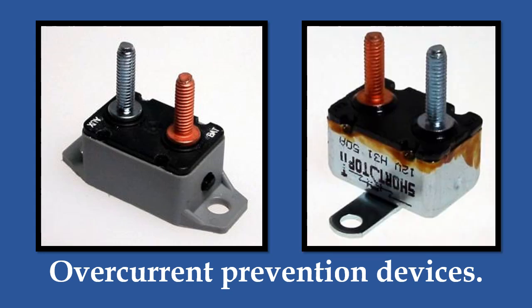With metal capped circuit breakers, which in this case is also an auto reset breaker, it will only reset itself after a time delay allows the breaker to cool down. These metal cap breakers also come in a manual reset model where the lead from one of the posts must be disconnected in order to reset the breaker.